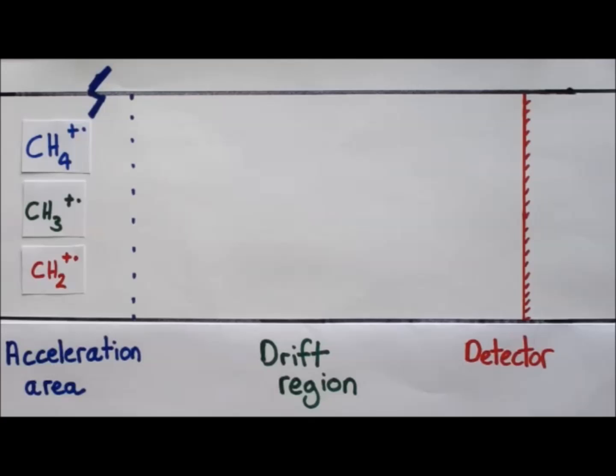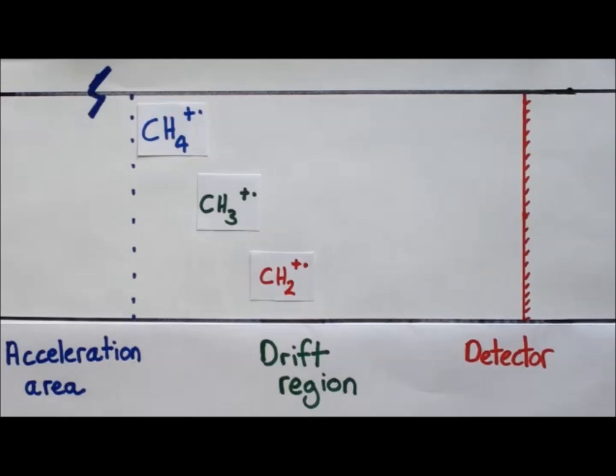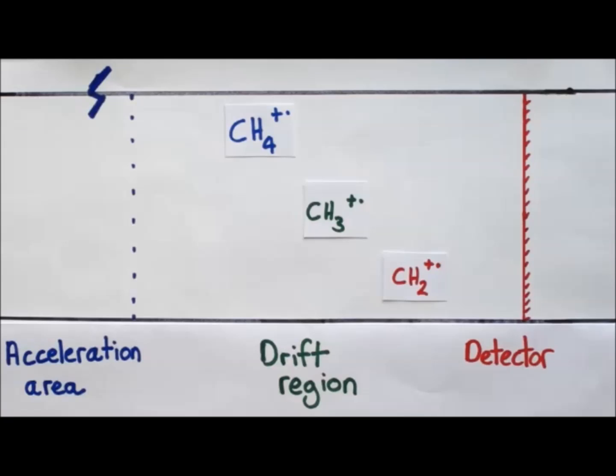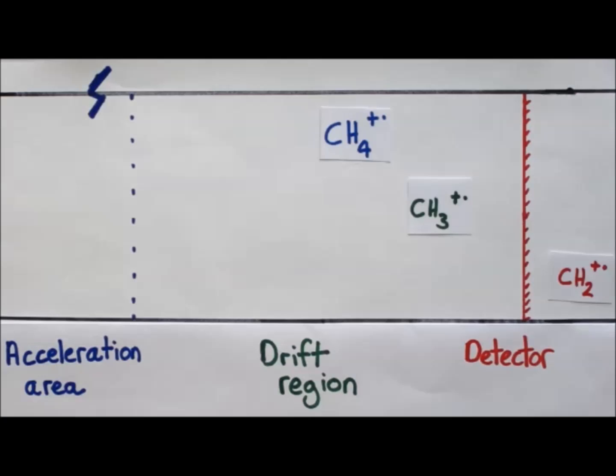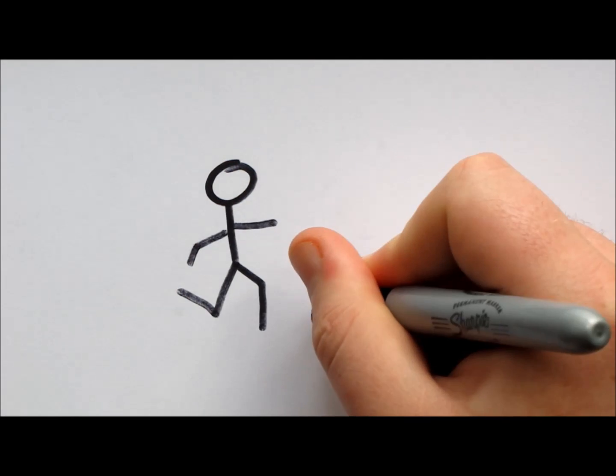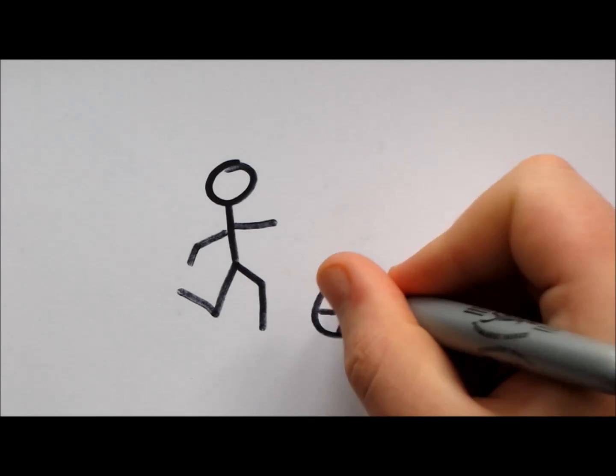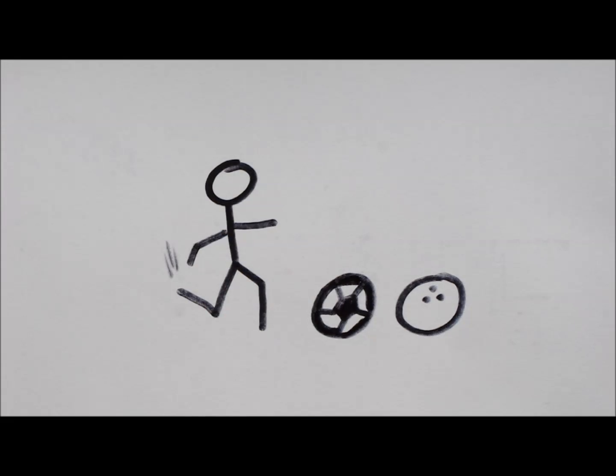The time of flight mass analyzer works by accelerating these ions in an electric field. All ions receive the same amount of potential energy from this electric field, which is converted to kinetic energy. The ions then travel down the flight tube, known as the drift region. The ions separate out because the heavier ions will reach a lower speed than the lighter ones. In the same way if you kicked a football and a bowling ball at the same time with the same amount of force, the football would fly off much quicker.